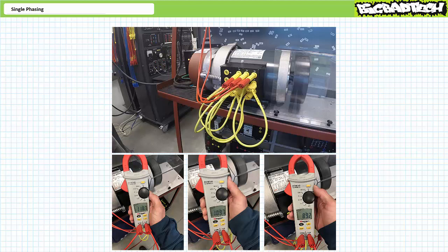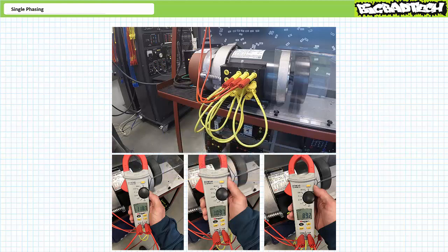Here's an additional rather surprising observation: what's the voltage across the third winding — the one that's lost connection to phase L3? If you said zero volts, you're wrong. A voltmeter measuring the voltage across winding three demonstrates it still experiences an 89-volt differential. What is going on here? Here's a hint: what types of interactions occur between movement, magnetism, and electricity in a spinning motor? I'll explain the source of this odd reading in a moment.